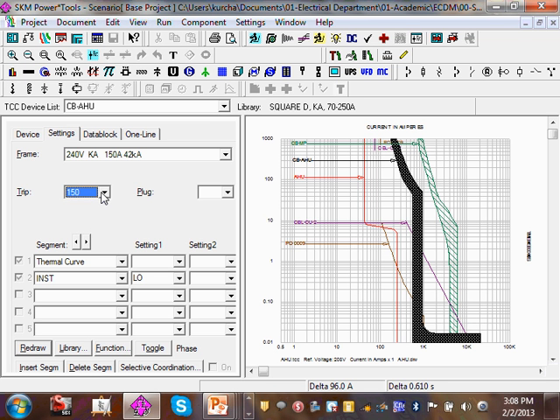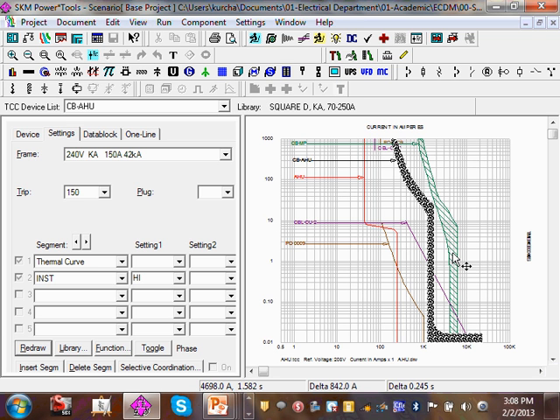In most applications, what I did right here, guys, will be a completely different circuit breaker for this series. And look how, if I move it this way, how high I can move. Look at the amount of energy now I'm allowing to stay if I have a ground fault in my chiller. I hope what I'm trying to get into, guys, is the lower the setting for the instantaneous, the more protection you have for you and your people when you're working energized. Cool. So that's one curve.